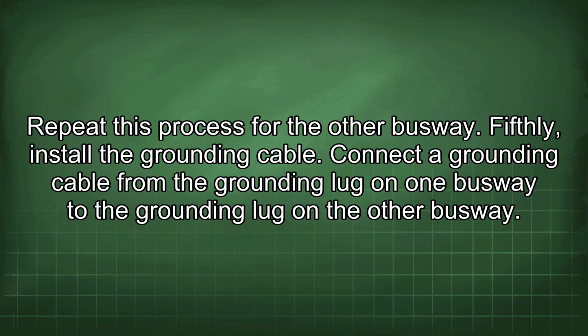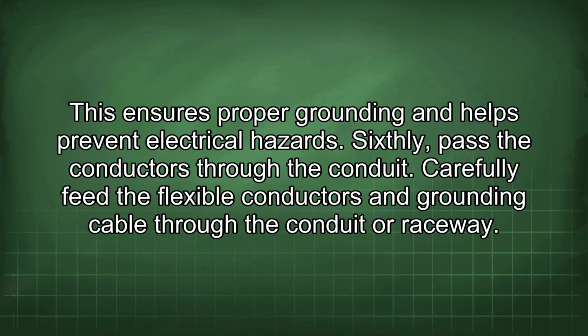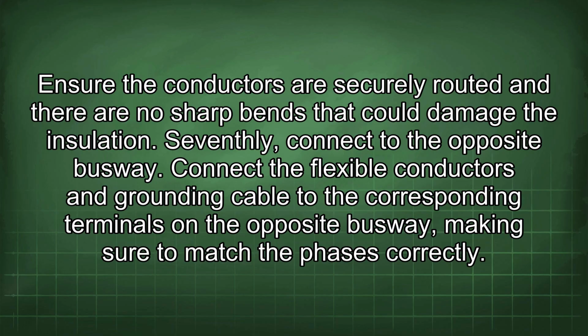Fifthly, install the grounding cable. Connect the grounding cable from the grounding lug on one busway to the grounding lug on the other busway. This ensures proper grounding and helps prevent electrical hazards. Sixthly, pass the conductors through the conduit. Carefully feed the flexible conductors and grounding cable through the conduit or raceway. Ensure the conductors are securely routed and there are no sharp bends that could damage the insulation.